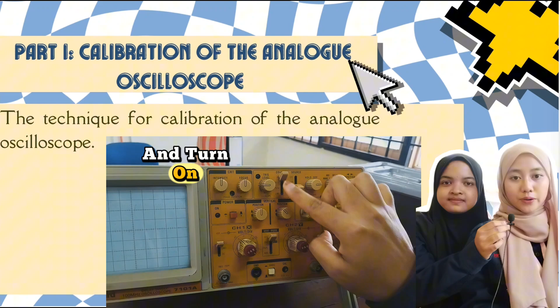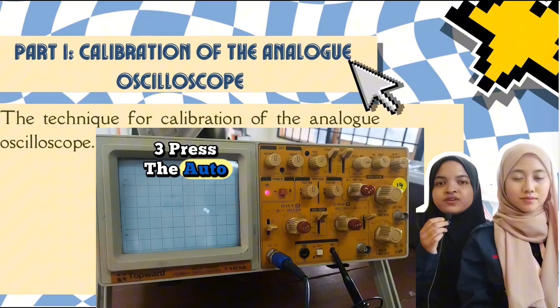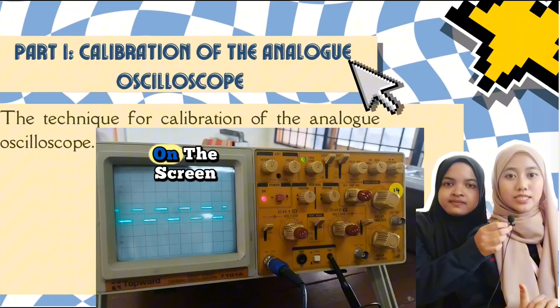First, connect the probe to the calibration terminal on the oscilloscope. 2. Set the volts per division and time per division knobs to suitable values. 3. Press the auto or cal button to display the calibration signal on the screen. 4. Adjust the vertical and horizontal controls until the displayed waveform looks like a stable square wave. When the square wave appears correctly on the screen, the oscilloscope is now calibrated and ready for measurement.